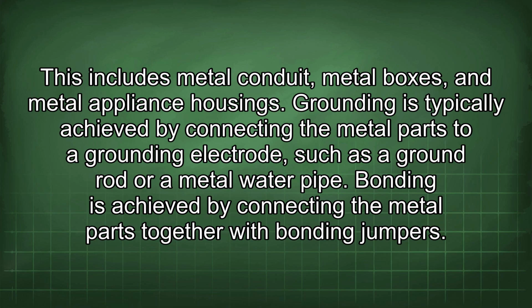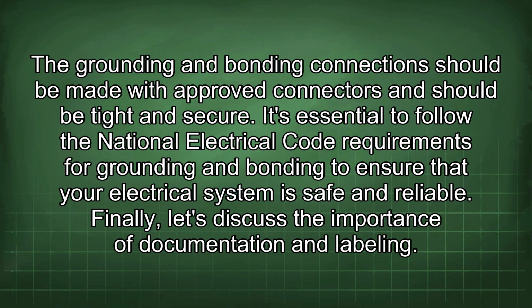Grounding is typically achieved by connecting the metal parts to a grounding electrode, such as a ground rod or a metal water pipe. Bonding is achieved by connecting the metal parts together with bonding jumpers. The grounding and bonding connections should be made with approved connectors and should be tight and secure. It's essential to follow the National Electrical Code requirements for grounding and bonding to ensure that your electrical system is safe and reliable. Finally, let's discuss the importance of documentation and labeling.